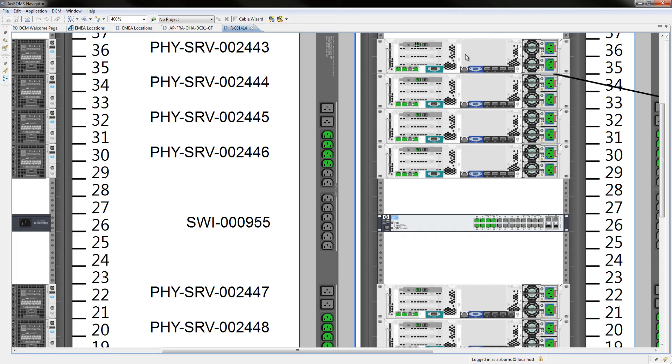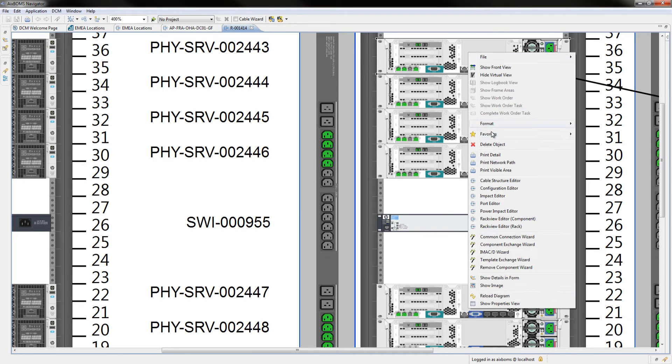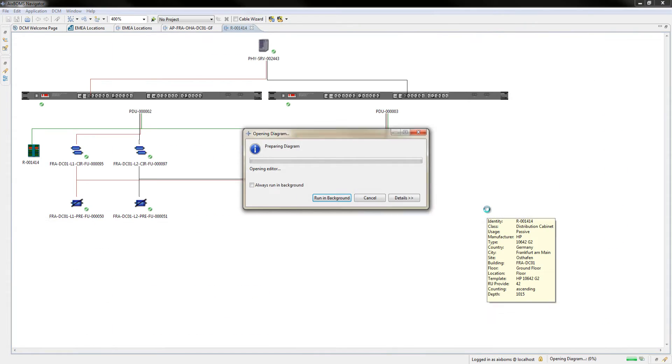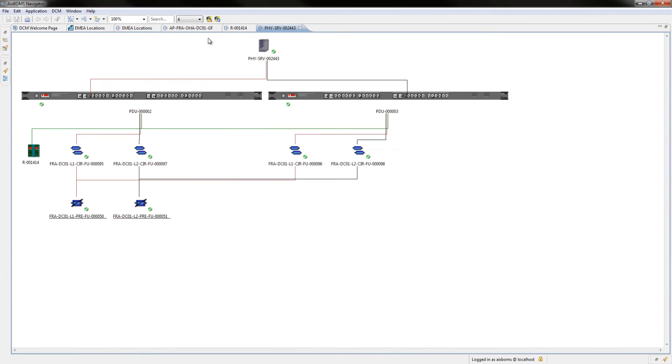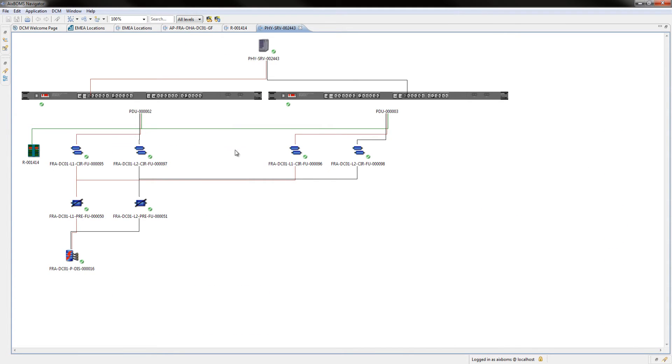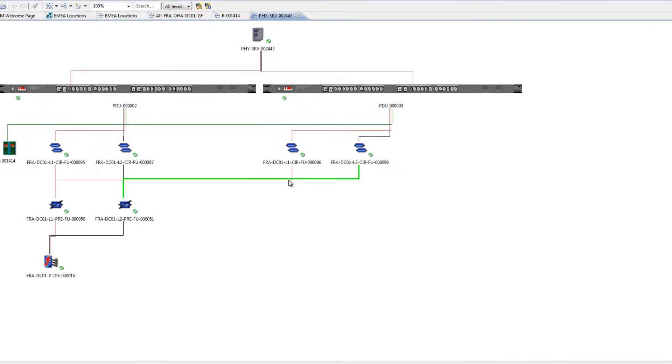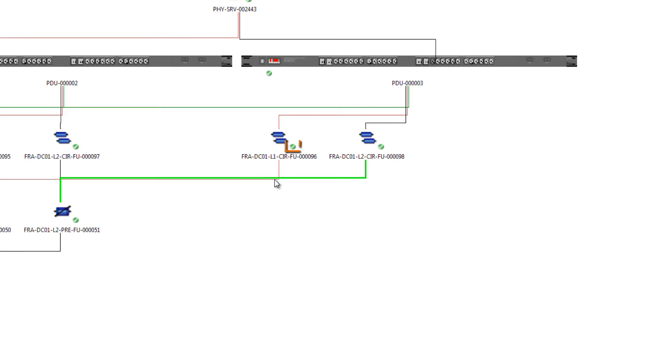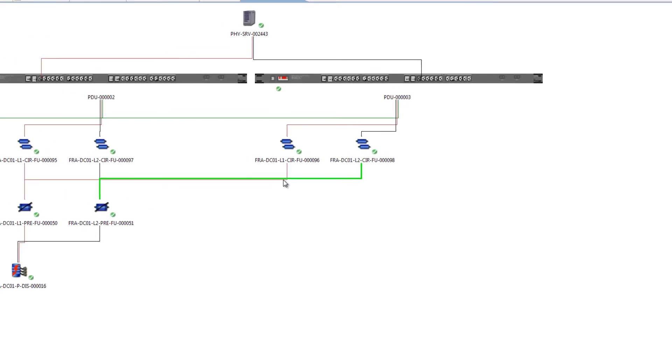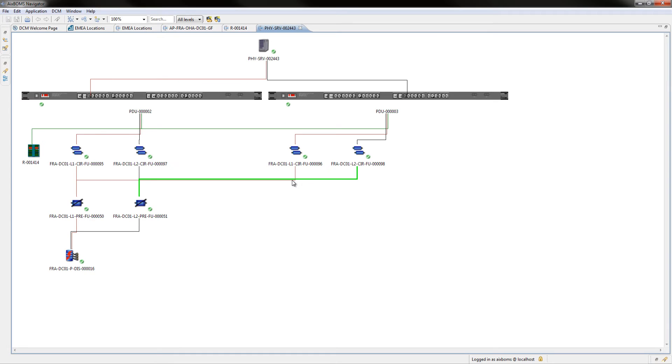Launching the Power Impact Editor provides a quick graphical overview of how this physical server is redundantly connected to phases L1 and L2 and the related objects in a power hierarchy. The green overlay icons next to the fuses indicate that there are currently no issues with the power supply.